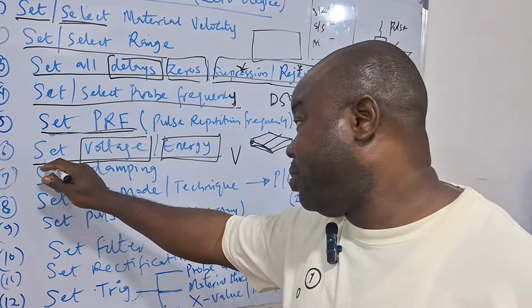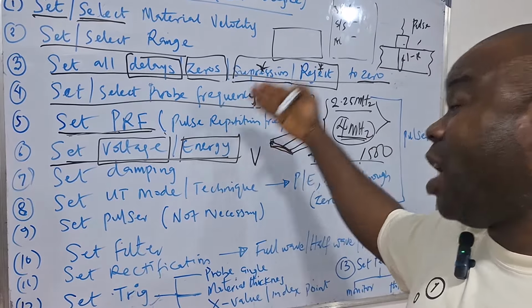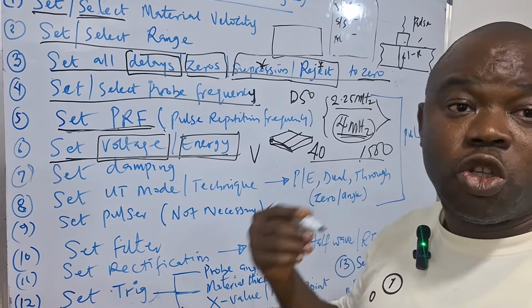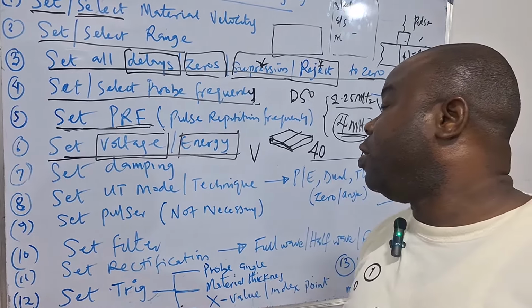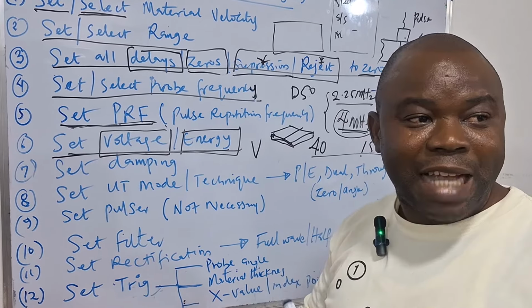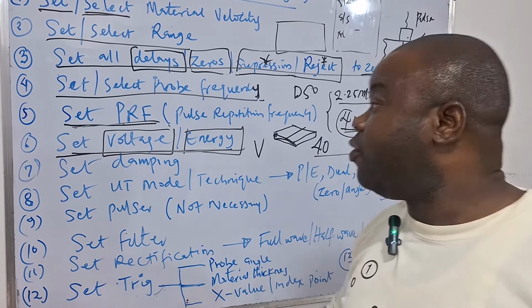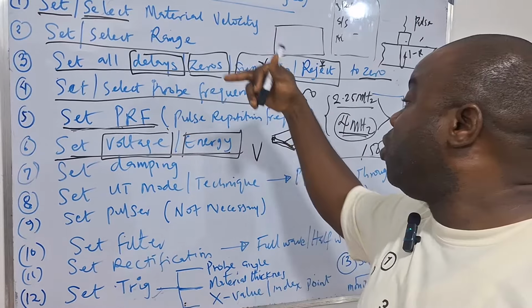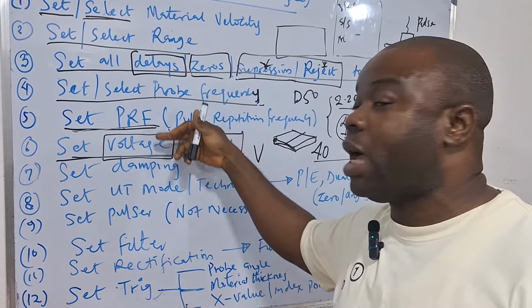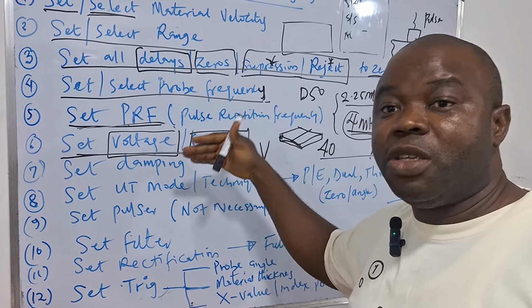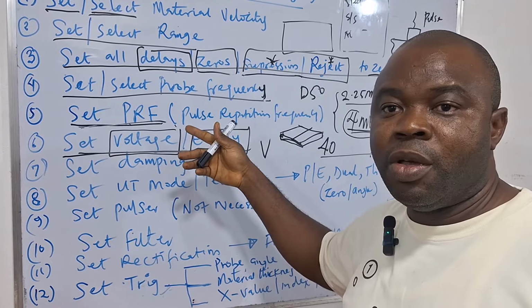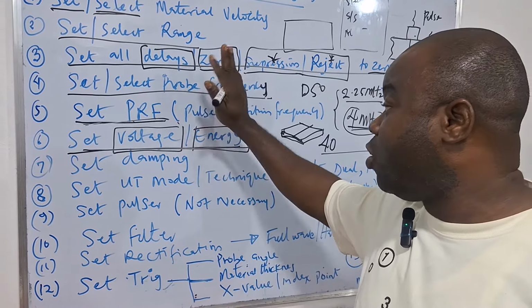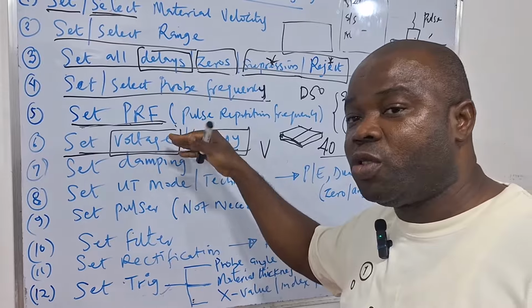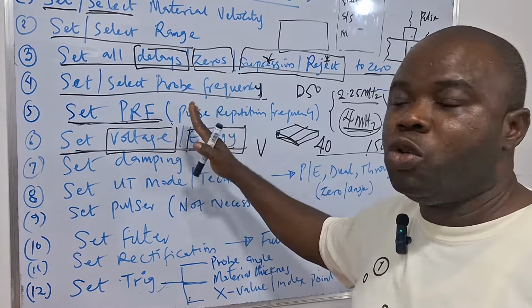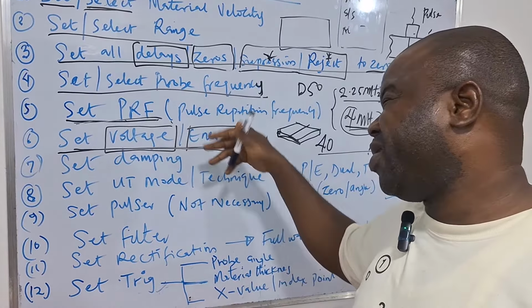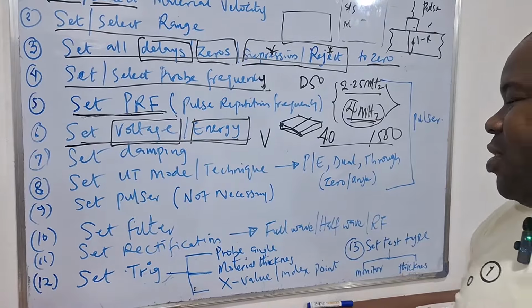So you want to keep the energy. If you are not sure, keep it in the middle. In some units, they will give you the option to automatically set it or manually do it. When you see auto and manual, even for PRF, the general rule of thumb is to use auto, because the machine will take the optimum PRF and the optimum voltage for you, so you don't have to go through the hassles of trying to adjust or determining which value gives you the right result.